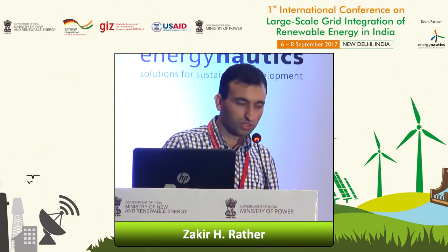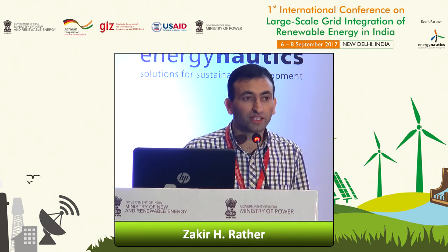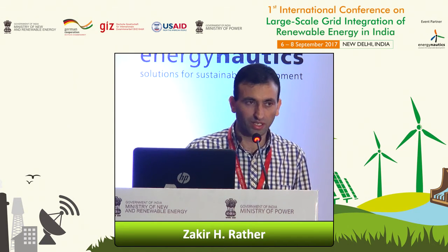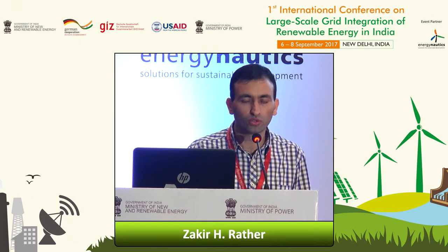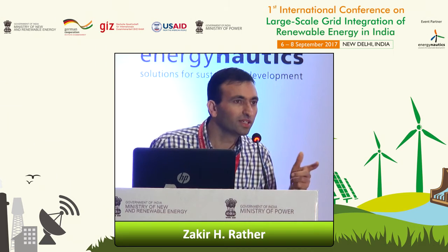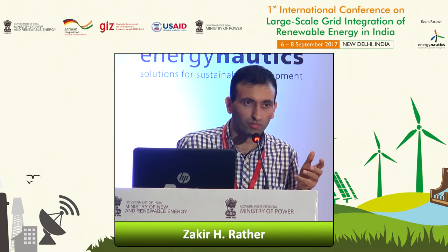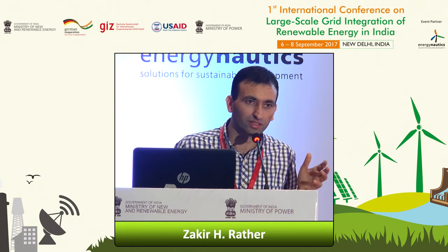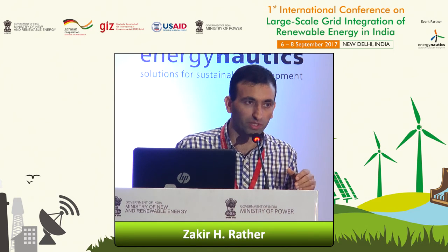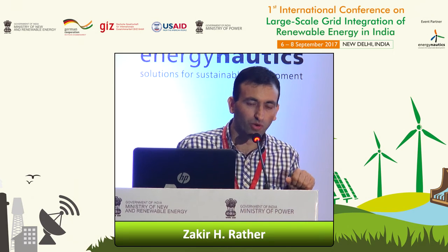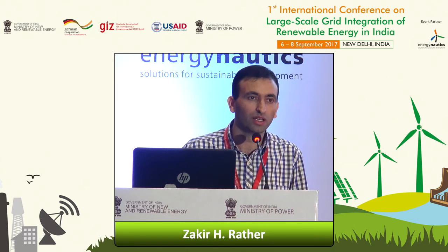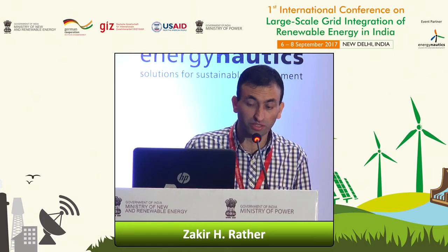So, coming quickly to wind farm modeling, there have been different attempts to model the wind farm, because there is a lot of difference between the wind turbine and the wind farm characteristics when we go to the modeling. So why do we need an equivalent model of a wind farm? For example, in some studies at the system level, where you have to model a lot of wind farms, and your study is, for example, a dynamic study, it just becomes impossible because of the computational burden and the complexity in the system. So we try to have an equivalent model of a wind farm, so that we reduce the computational burden and the complexity of the system while still retaining the high accuracy of the detailed model.